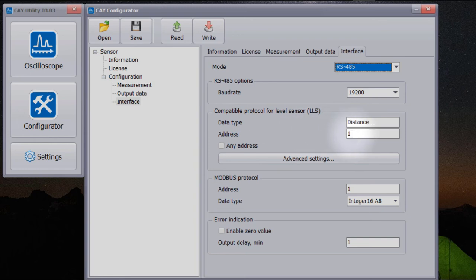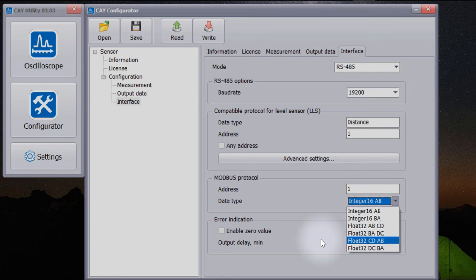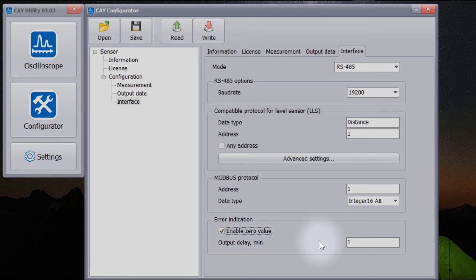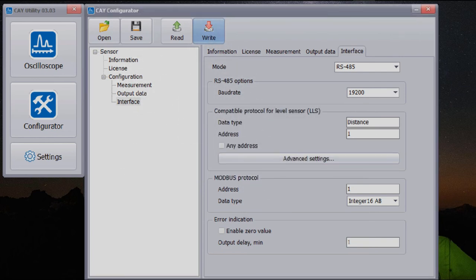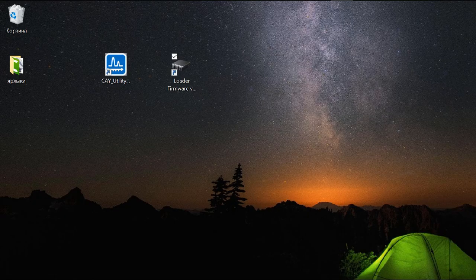We can also set up fuel level sensor protocol details, baud rate, type of data to be sent, and sensor addresses on the RS485 bus. Also, the sensor can provide data by Modbus protocol, and you can choose the Modbus data format there. The sensor will provide a zero value if it can't see the reflection signal, for example, when the tank is tilted relative to the horizontal surface, which is inconvenient when the sensor is installed on a vehicle tank. You can deny zero values as output. The sensor will send the last actual data instead. Or you can set a period of time after which zero value output can be allowed after a period of neutralization. Save settings with this button. Also, you can save the sensor configuration in a file and upload it to the next sensor.